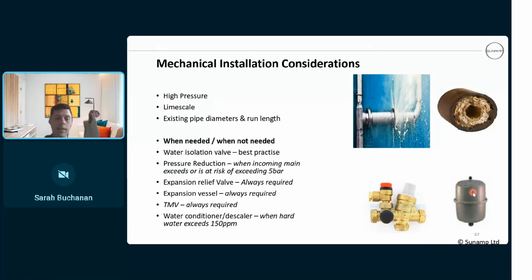All right. So now you've got your expansion relief always required, which is fine, and this combination valve, which is fine to use as well. So check valve and expansion relief downstream of that. What do you think might happen out of this expansion relief valve if the air charge went flat or to zero on that vessel? Can anybody tell me?